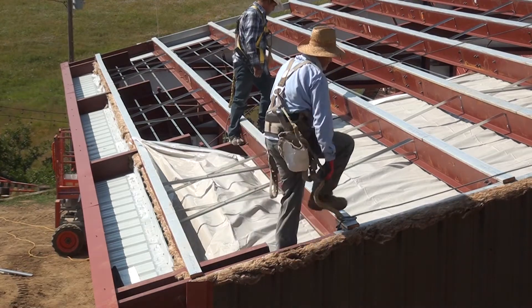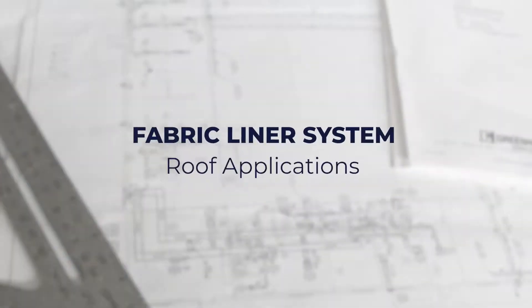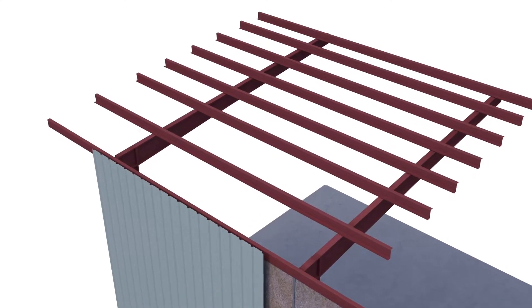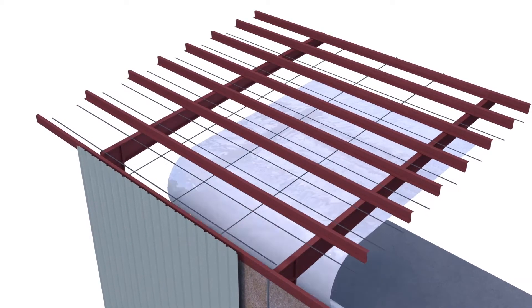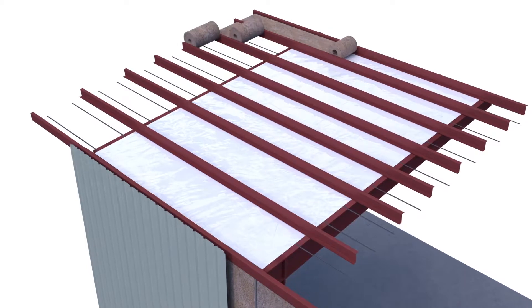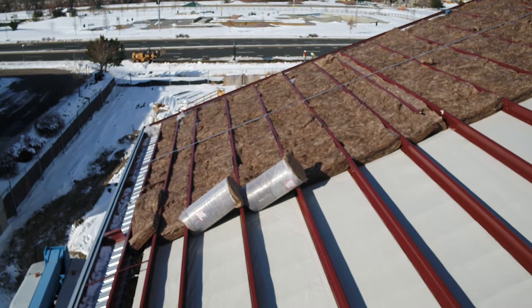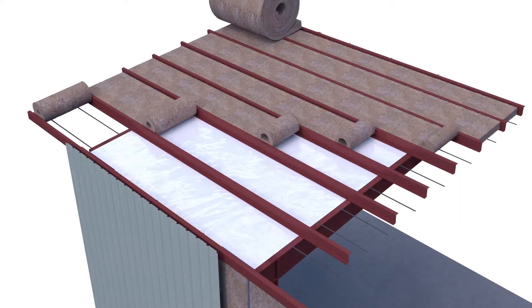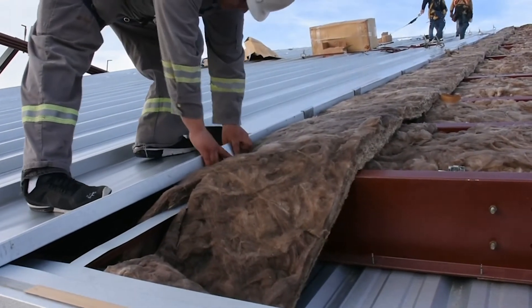This system can be installed on both roofs and walls. In roof applications, a woven network of steel bands are installed with the fabric on the underside of the purlins, concealing them. A first layer of unfaced insulation is rolled in between the purlins, running the length of the building. A second layer of unfaced fiberglass is installed perpendicular over the top of the purlins from peak to eave. Roof panels are then installed over the top.